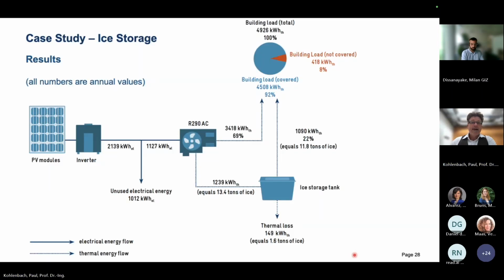Let's have a look at results from the ice storage. What we see here is basically an overview of the system. We have the PV modules, inverter. We then run AC, electrical energy, into the R290 air conditioner. That's the outdoor unit from the previous slide. Here we convert electrical energy into thermal energy. Some of it goes into the ice tank. That's the way down here. And some of it goes directly into the air conditioner. Of course, during the day when the sun is shining, we can run the air conditioner straight off the PV panels. The building load in total is the 4.9 megawatt hours, the number given up here.